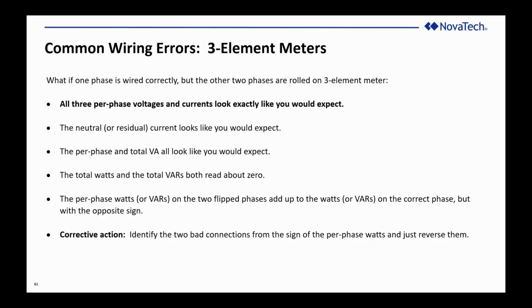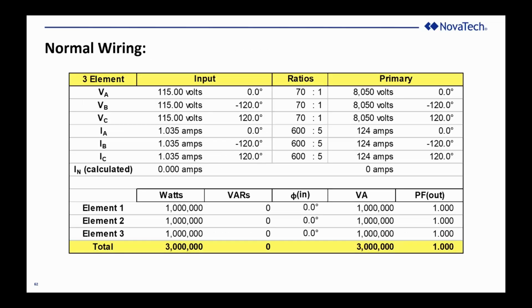The per phase watts or VARs on the two flipped phases will add up to the watts or VARs on the correct phase, but with the opposite sign. That's because the power factor is now minus 0.5. So identify the two connections that are flipped, flip them back, and you're fixed. Here's what it looks like.